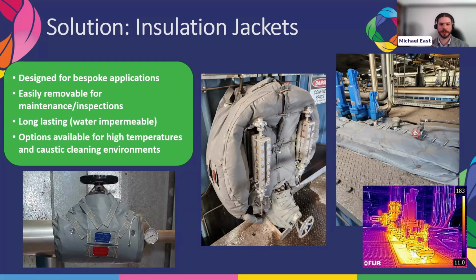The way we look at this process is we go through the entire site with the thermal imaging camera, and we end up with a line-by-line list: these are your flanges, valves, etc, this is the thermal loss associated with each line item, and the cost to insulate each one. So you can quickly work out how to fit this project into your capital limitations or financial criteria. You might have some 40-50 degree hot water that needs insulation, but it's going to have a slightly longer payback, and if you want to control that to 2 years, you might want to cut out that hot water piece. We prefer to group the whole lot together, but it does give you the flexibility to fit in with financial limitations.